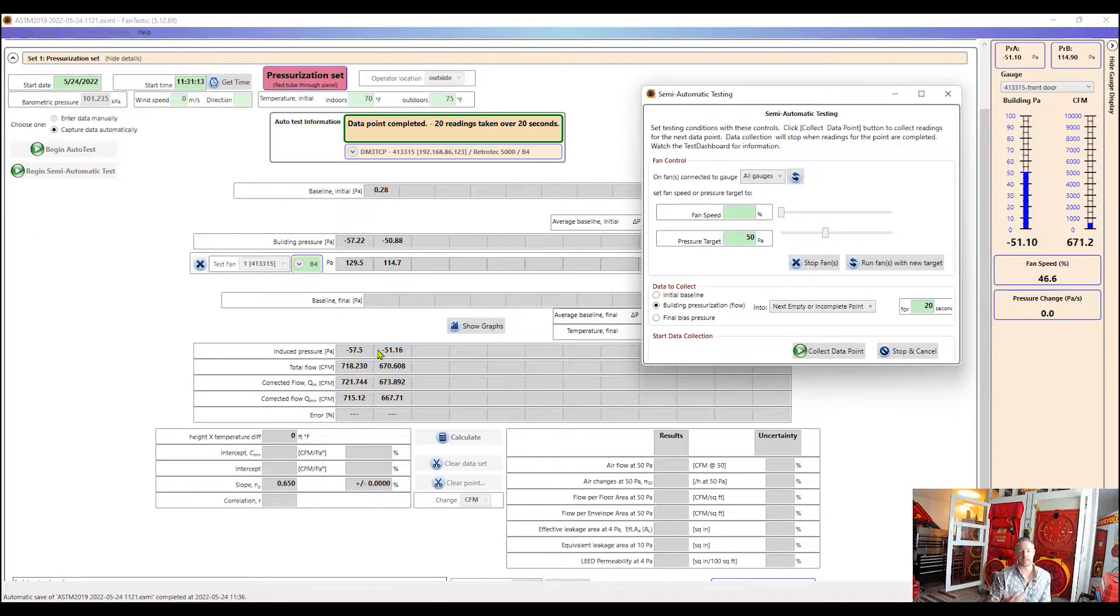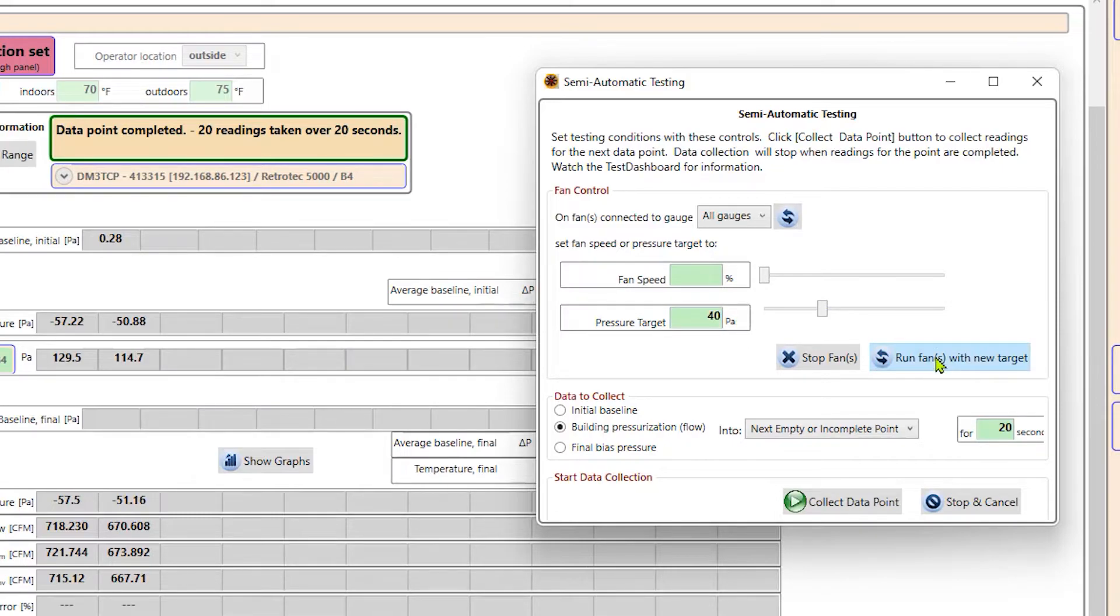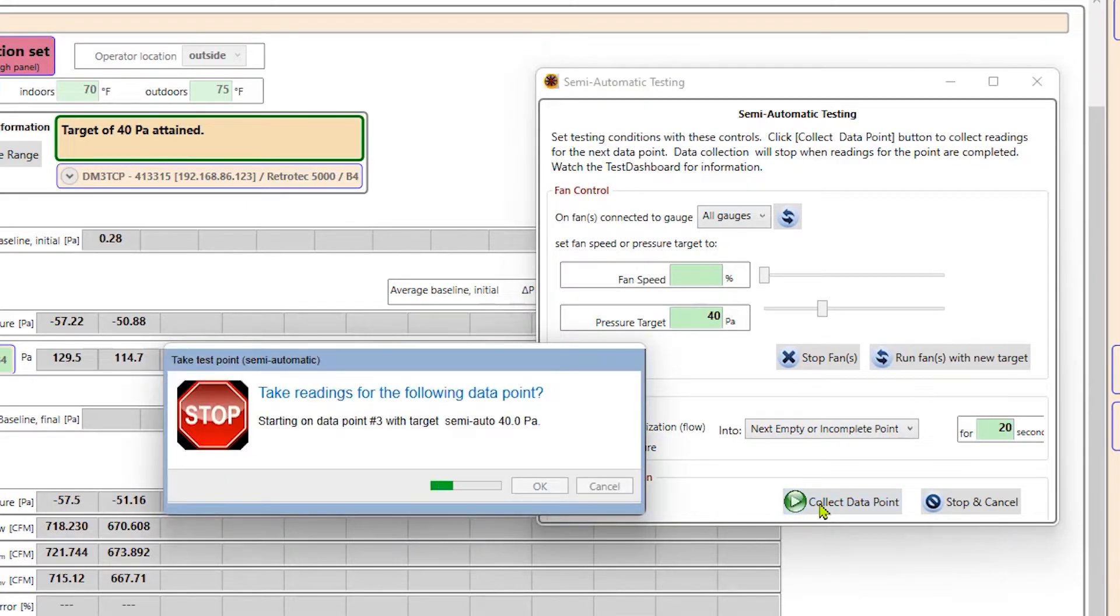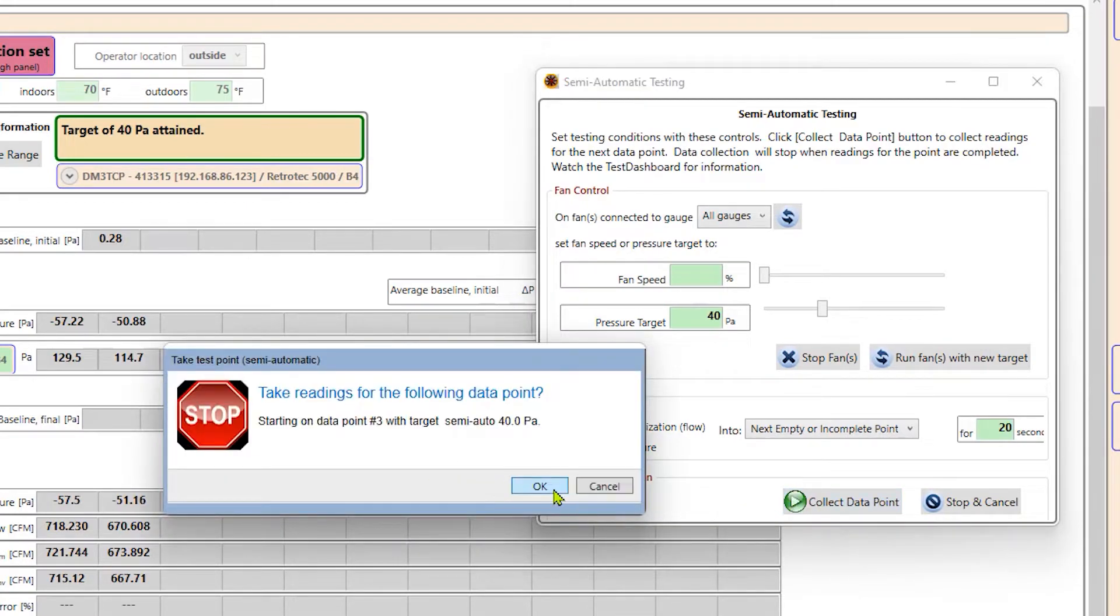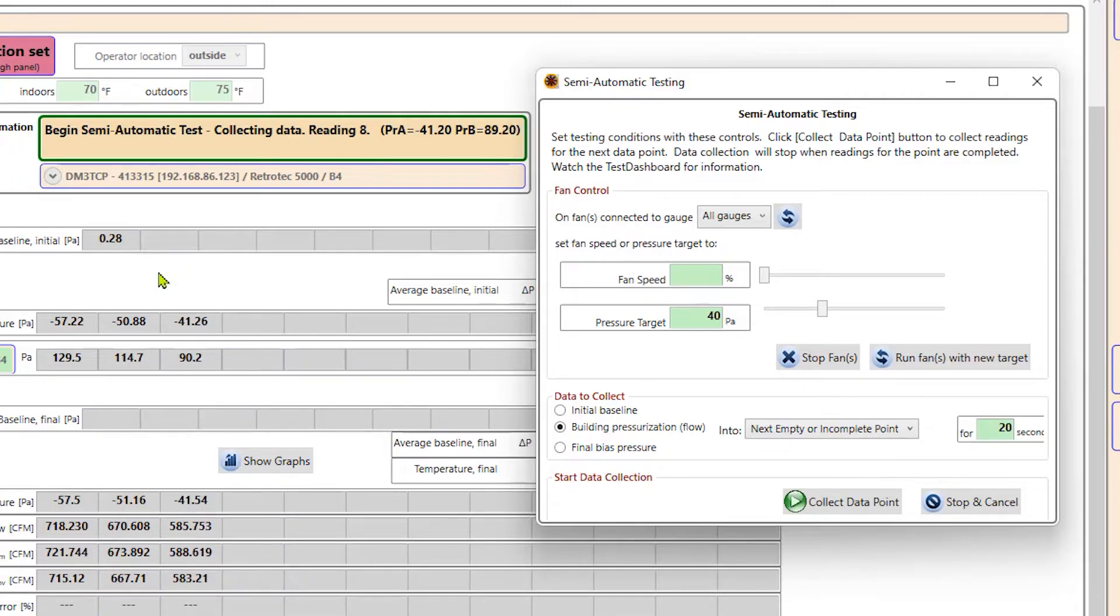Now that that one's been completed, we'll do one more. We'll go ahead and drop it down to 40. Tell it to run fans there. And now we can see a pressure of 40 Pascals has been attained. And so we'll go ahead and collect data. And now we'll see it populate here in our third column as it starts collecting data for 20 seconds.